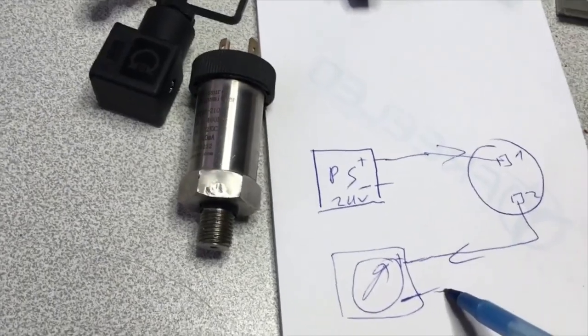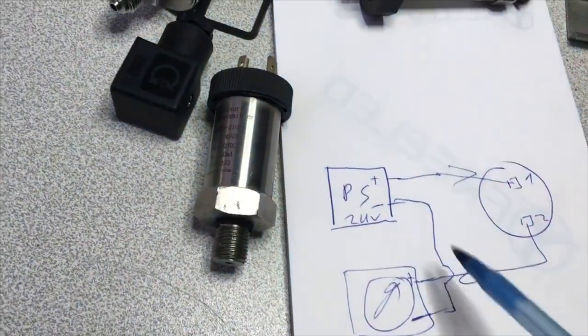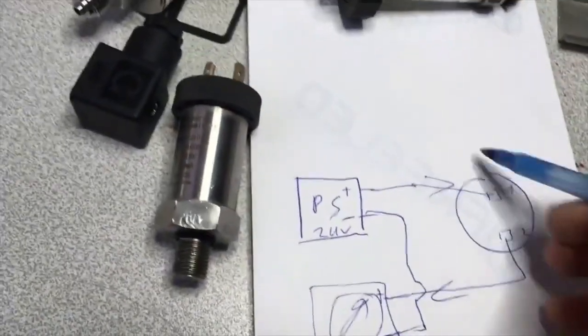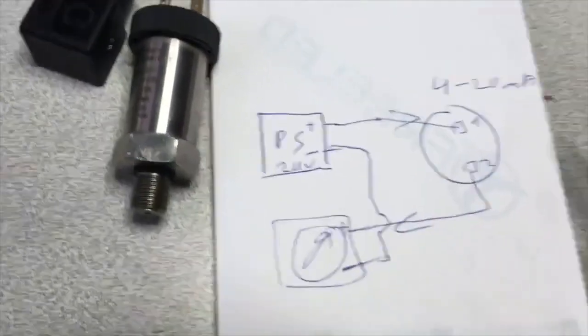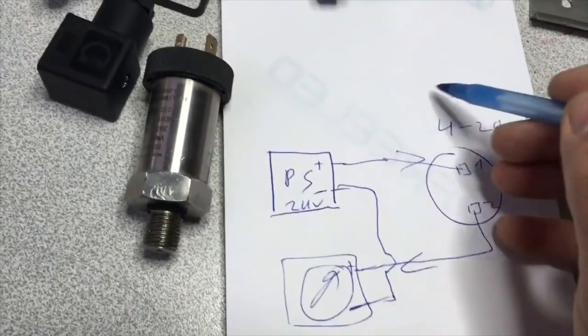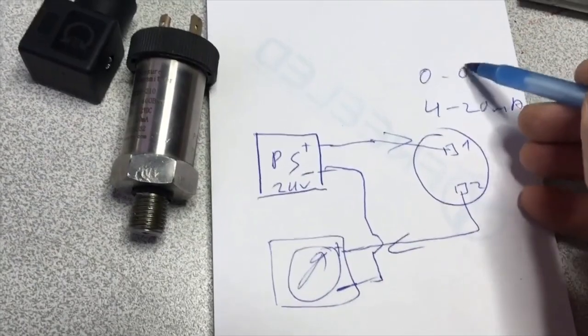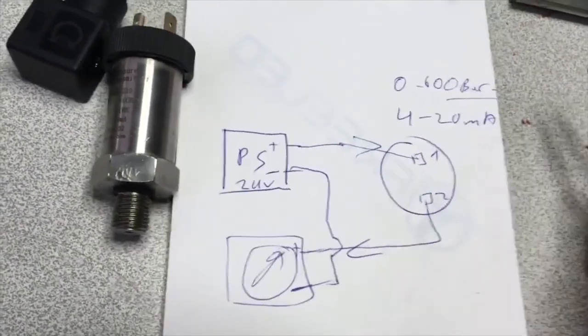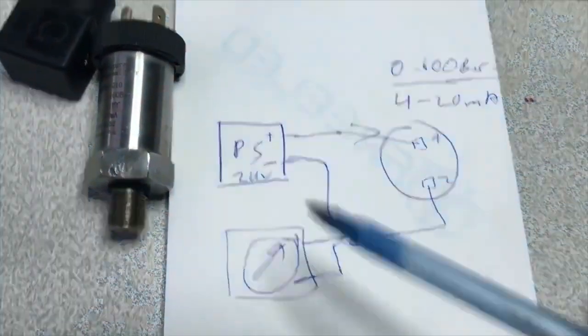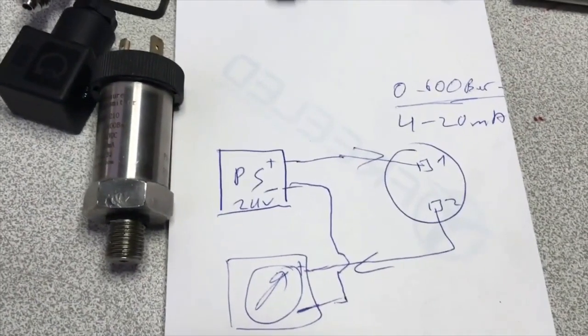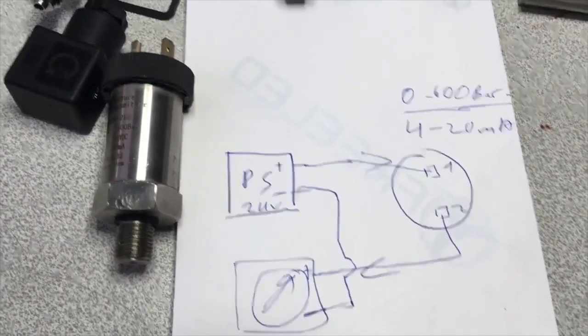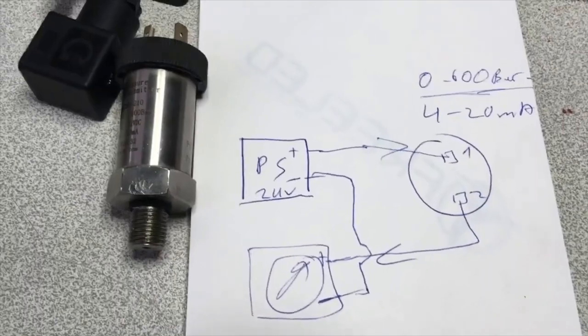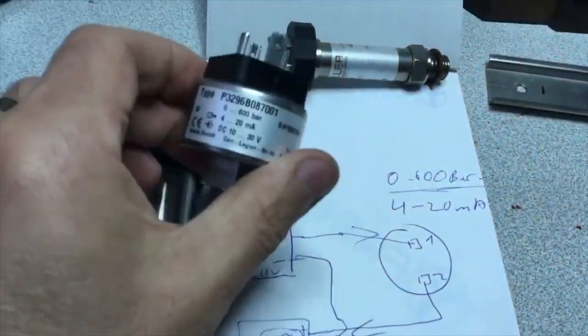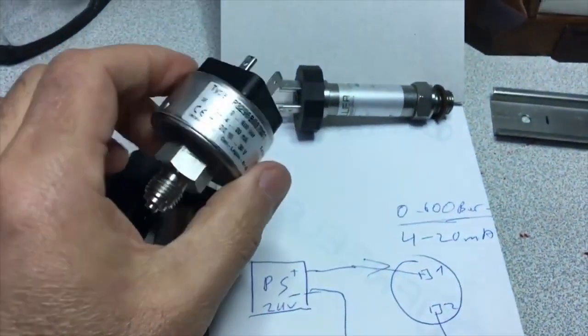Again plus we go to the end. We take the minus end from here again. We connect it to the minus end of the power supply. So we have established a series circuit. This is a current of 4 to 20 milliamperes. Of course, we mentioned that the sensor we have is 0 to 600 bars. Of course, this is 0-600 bars and this is a unique value for this sensor. There are different values in different sensors, or we prefer a suitable sensor for our purpose.